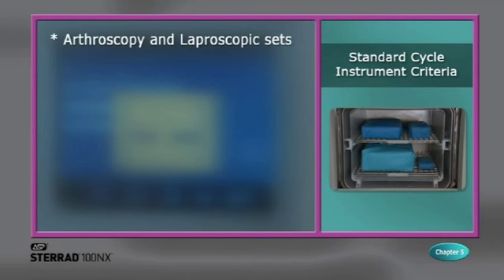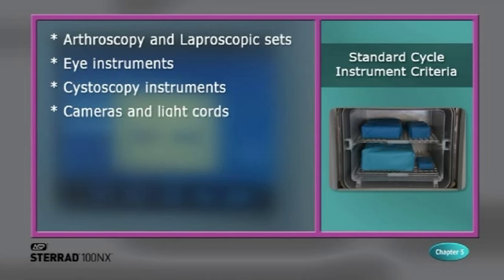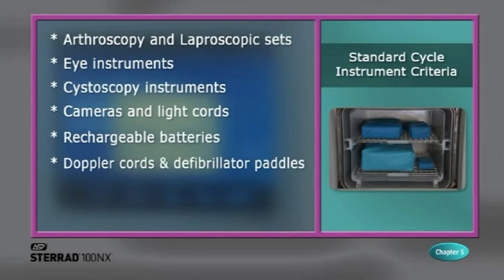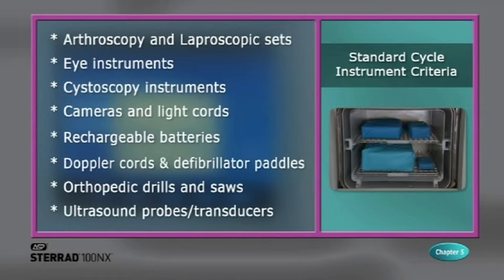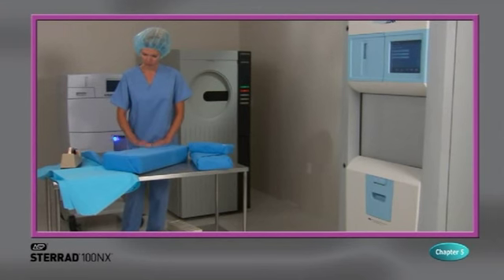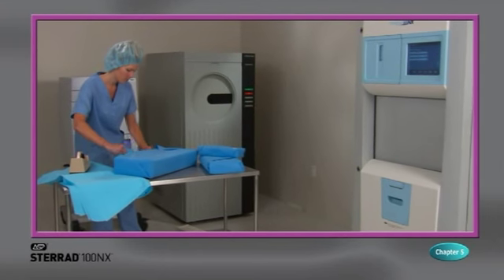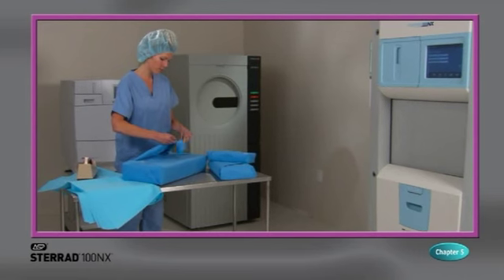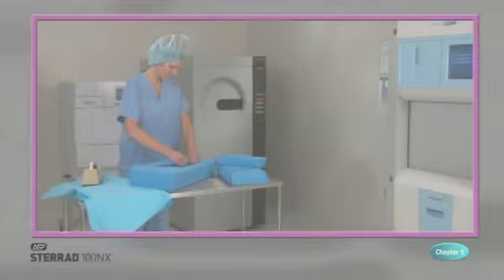Instrument sets that can be sterilized in the standard cycle include, but are not limited to, arthroscopy and laparoscopic instrument sets, eye instruments, cystoscopy instruments, cameras and light cords, rechargeable batteries, Doppler cords and defibrillator paddles, orthopedic drills and saws, ultrasound probes and transducers. When constructing the load for the standard cycle, the total weight of the load to be sterilized should not exceed 21.4 pounds or 9.7 kilograms.